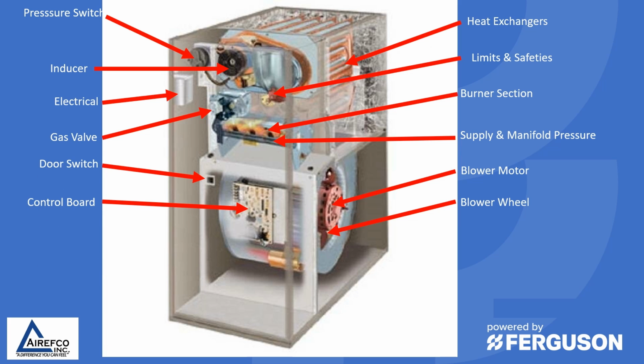And last but not least, the door switch. Most of you guys have devices to bypass these, or you put duct tape or electrical tape over them. Whenever you're done working on the furnace and troubleshooting it, make sure you take those devices off and take your tape off. If a homeowner would happen to open the door and you've left a tape on this door switch and they stick their hands into high voltage, it could become a real liability issue. So make sure that you return the furnace to proper operating condition once you're done examining and troubleshooting the furnace.